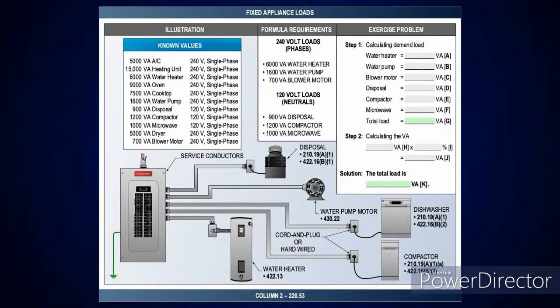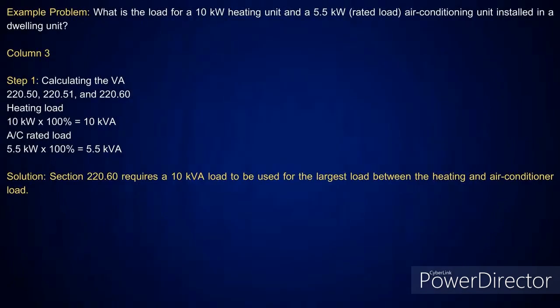Now, all right, right here, I'm looking at this illustration. Okay? I automatically know AC, heating, oven, cooktop, and dryer load do not go. Everything else left is there in the fixed appliance load when you do this calculation. I have 4 or more, so I'm going to take it at 75% to get that total load. All right. And then you come to the last one before we get to the largest motor load.